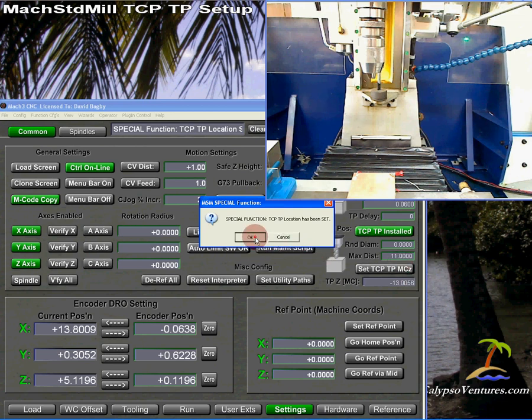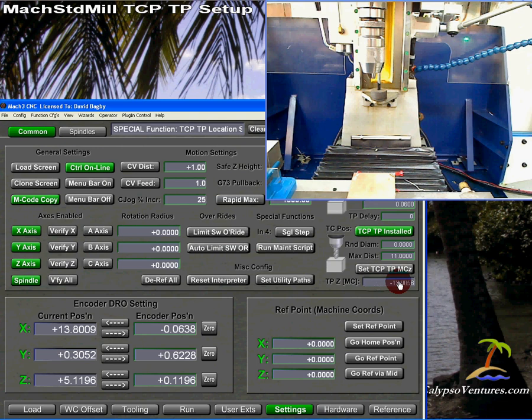plate. I will say OK to exit the dialog box, and you will notice that the touch plate is positioned on my machine at minus 13.0056 in machine coordinates. Now, the number you saw here before was a different number because I had purposely done this operation before starting the video to make the number wrong so that we could see how it corrects it. In any case, that is the end of the process for calibrating the touch plate. Now that the system knows where this is, you can use this for tool changes, and it can be used to measure tools on the machine.